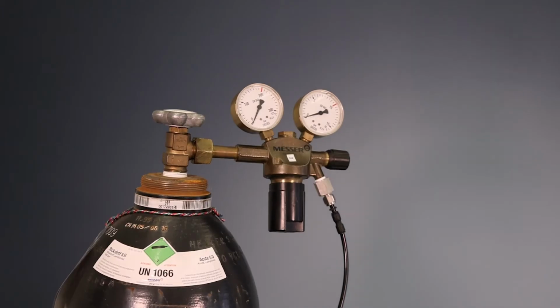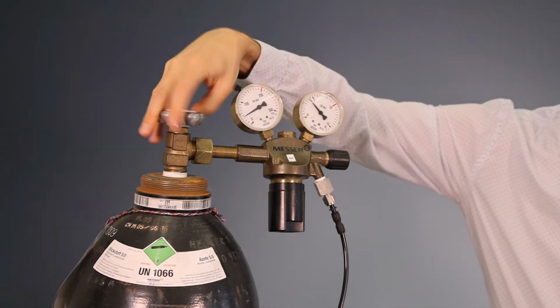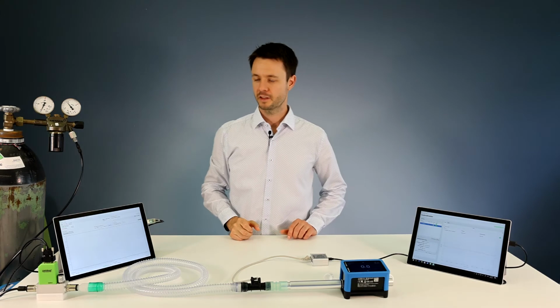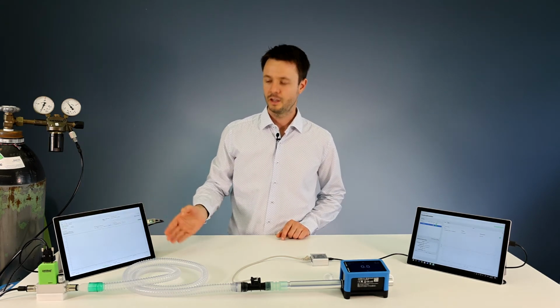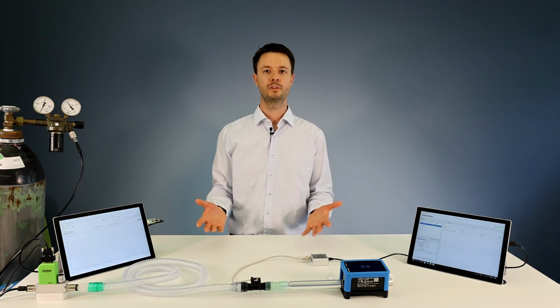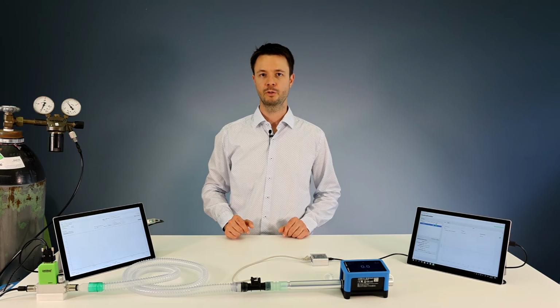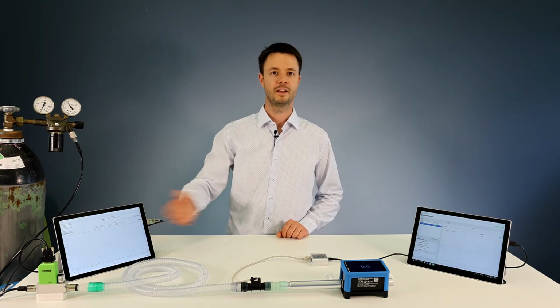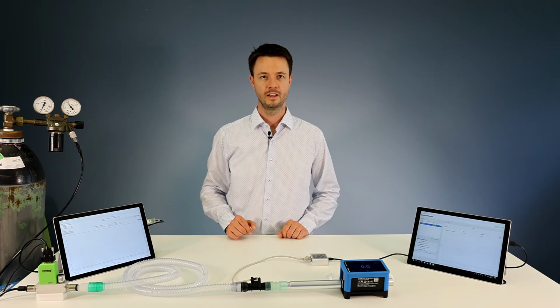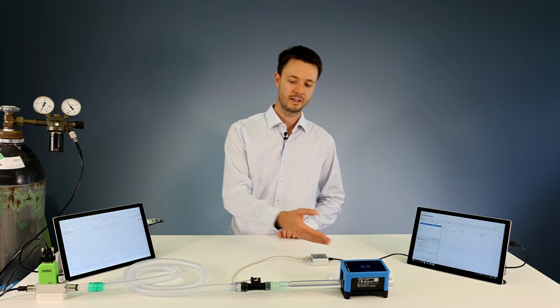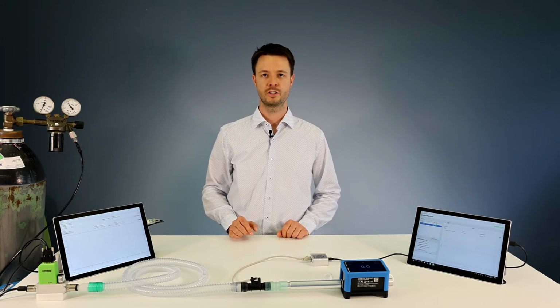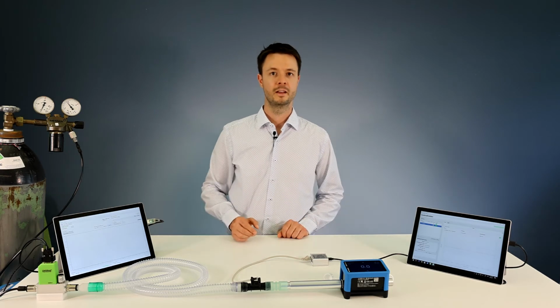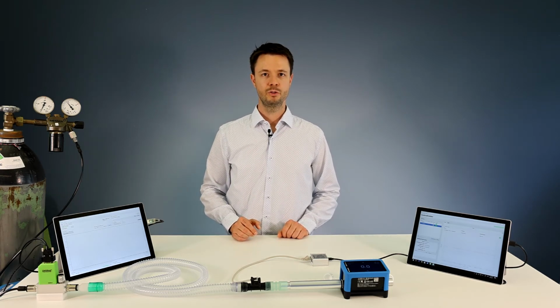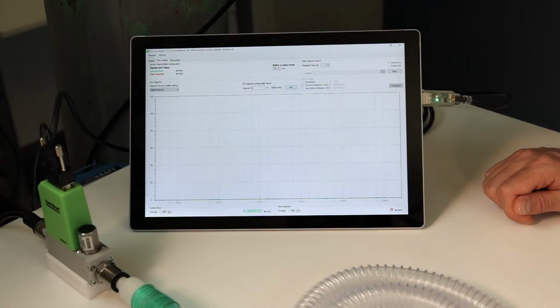Now, with everything connected, we're ready to start the actual test by opening the gas bottle to build up the pressure in our mass flow controller. Nothing is happening yet, as the flow is currently set to 0 and the valve is still fully closed. What would you expect to happen if I enter a set point of 70 liters per minute in our control software? Well, the accuracy of the mass flow controller is specified at ±1%, and the accuracies of the reference, the Cytrex H5, and our flow sensor are both around 3% of the measured value. That means, for a set point of 70 liters, I would expect the two flow sensors to show measurement values between 67.2 and 72.8 liters per minute. Let's see what happens and start the measurement by entering 70 liters per minute.